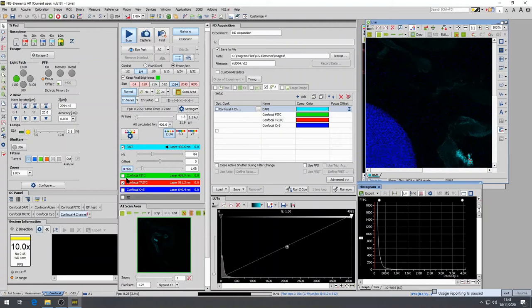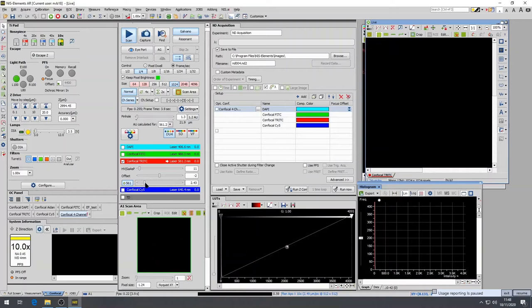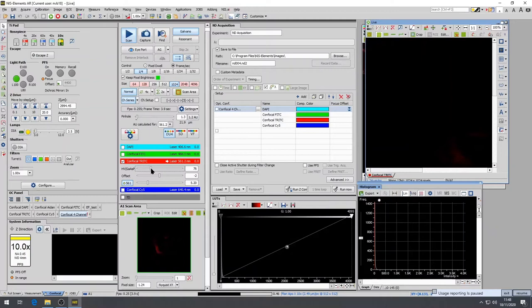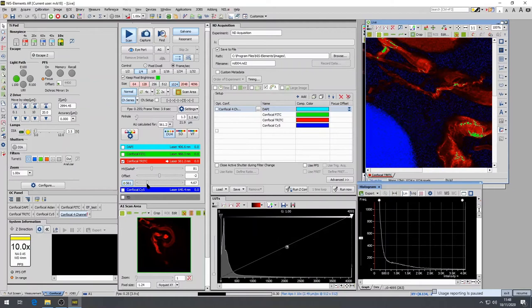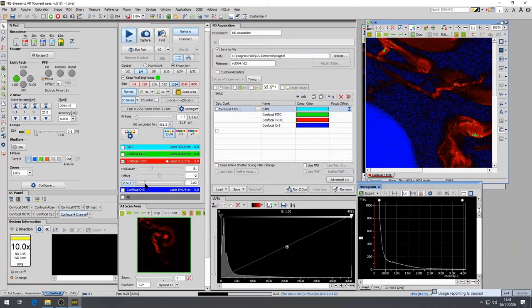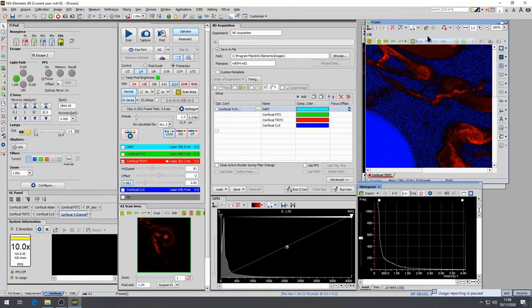And then finally, I move on to the third channel. I find the sample by increasing the laser power. Remember, this should be between 5 and 8. And the PMT gain should be between 80 and 120. So in this case, the oversaturated pixels are shown in green. I'll make sure I reduce the number of oversaturated pixels by decreasing the laser power. And then once I'm happy with this, I'll make sure that all these over and under saturated pixels will have no color association. And then I'm ready to capture the images.